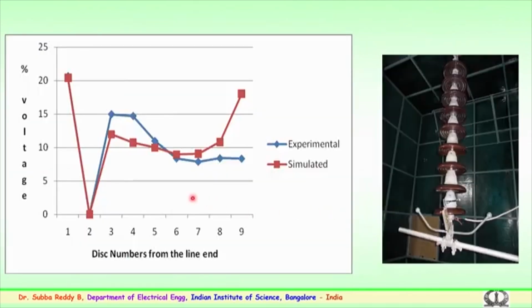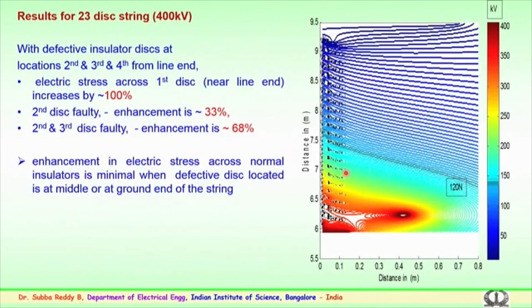These are some experimental and simulated results in the laboratory for a 9 disc insulator string, where we have tried to see the failures; faults have been intentionally created and the study has been done. So, overall, when you look at the results for a 400 kV transmission system, consider the case where the defective insulator happens to be in the second, third or fourth position from the line end, that is, the high voltage end.